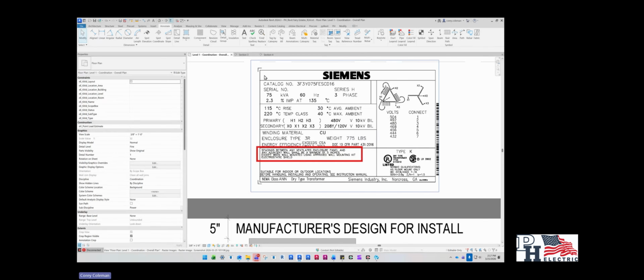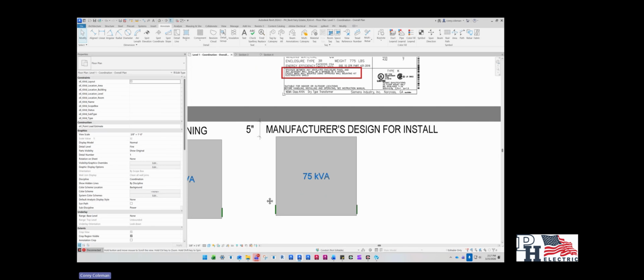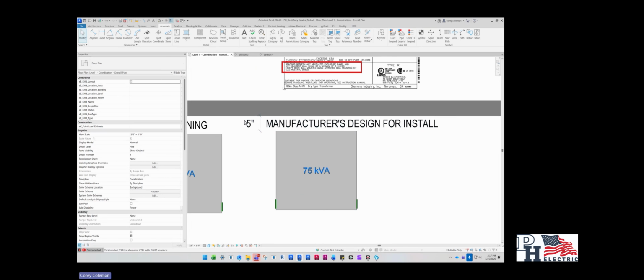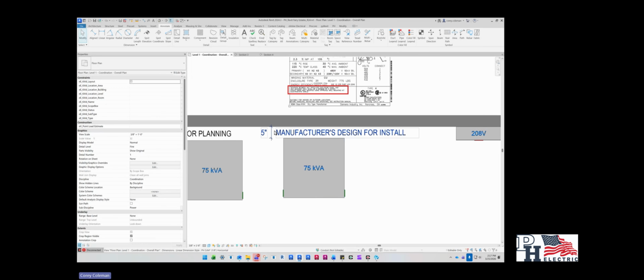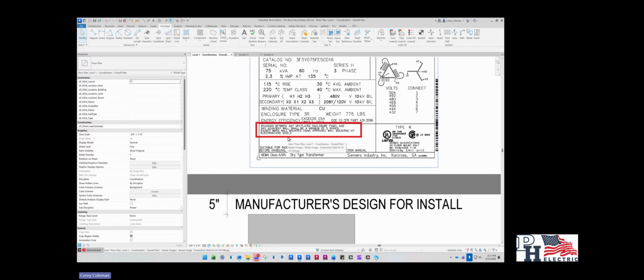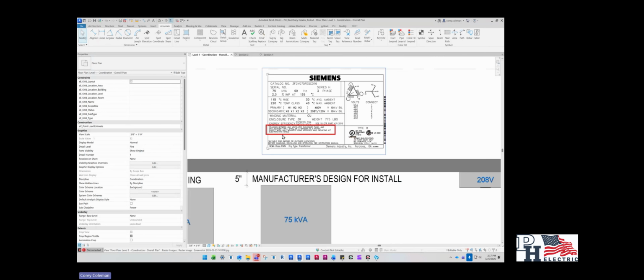So for instance, this is a transformer from the Novo job. It is calling out for 5 inches of space between any adjacent wall. So you would then update your design to capture the manufacturer's design for the install. A lot of the transformers I see nowadays are actually going down to even 2 inches or even less. So it's also worth looking at the transformer spacing recommendations so that you might be able to save some space in your electric room.